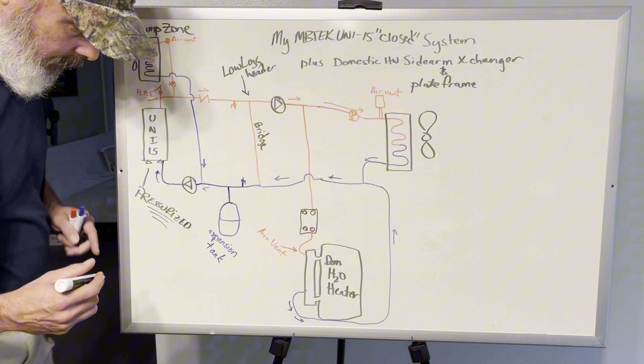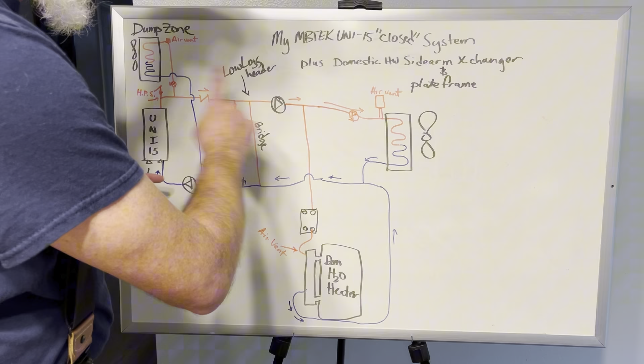So what I have, as we saw in the last video, is an MBTEK Uni-15 wood boiler. It is a pressurized system, so it does have high pressure safeties. When you have a pressurized system, temperature changes in the water, like between off cycles, can make the water volume contract. It can expand when it heats. So closed loop, you've got to have an expansion tank.